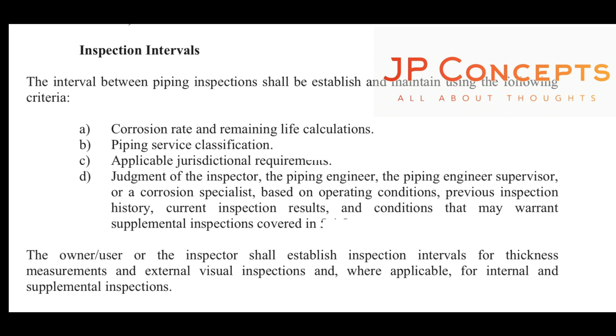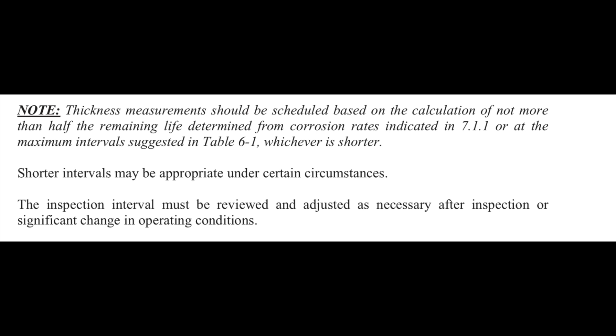This is based on operating conditions, previous inspection history, current inspection results and the conditions that may warrant supplemental inspection. The owner or user inspector shall establish inspection intervals for thickness measurements and external visual inspection as and when required, based on the condition of the system. Normally, the thickness measurement should be scheduled based on the calculation of not more than half of the remnant life. This half of the remnant life concept is very important in 570 calculations. Shorter intervals may be appropriate under certain circumstances. The inspection interval must be reviewed and adjusted as necessary after inspection or significant change in operating conditions.